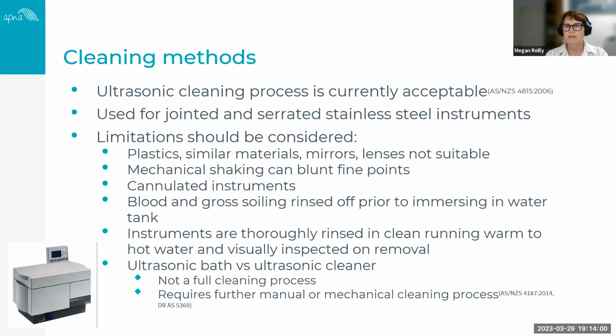Before you put items into an ultrasonic cleaner, you need to remove that gross soiling, so it needs to be rinsed prior to immersing into the tank. And then when you remove those instruments, you must thoroughly rinse them in clean running warm to hot water, and then visually inspect them to make sure that they are in fact clean.